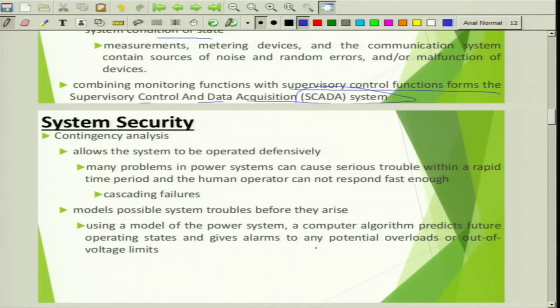So, next is contingency analysis. First is monitoring, next is contingency analysis. This is the second important function of system security. It allows the system to be operated defensively. Many problems in power systems can cause serious trouble within a rapid time period, and the human operator cannot respond fast enough. So, this leads to cascading failures. So, it models possible system troubles before they arise. Using a model of the power system, a computer algorithm predicts future operating states and gives an alarm for any potential overloads or out of voltage limits. There is a famous saying in English, prevention is better than cure. So this is what we are planning here: forecast the future issues and ensure that you are ready to receive those kinds of critical contingency events.